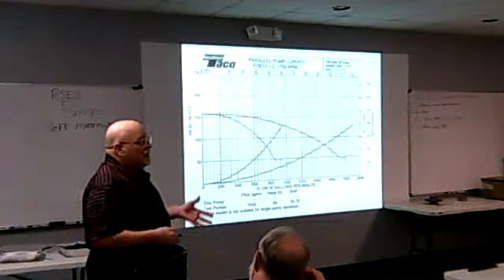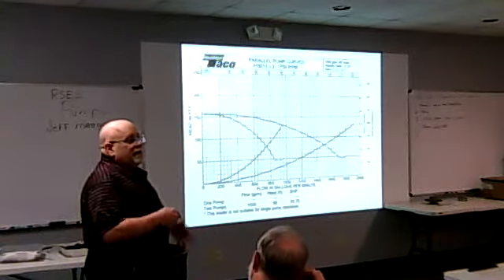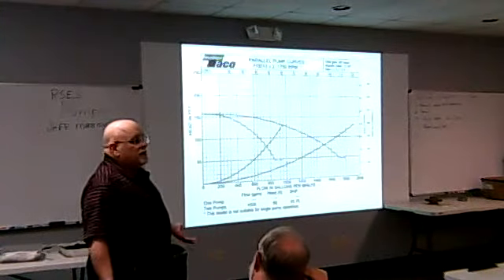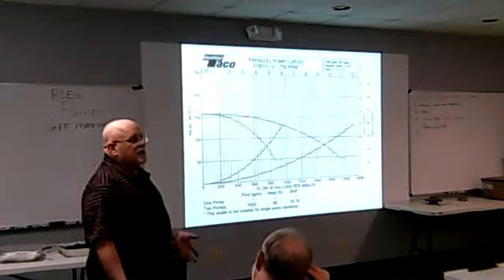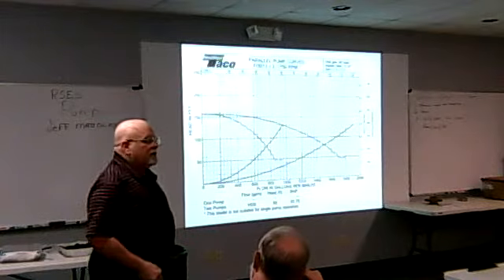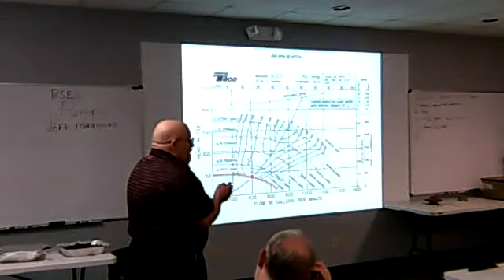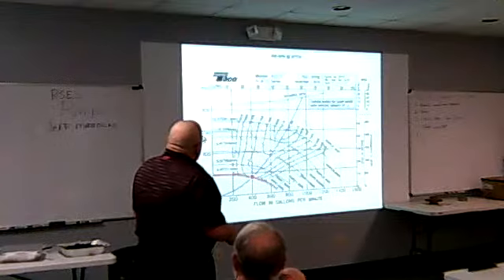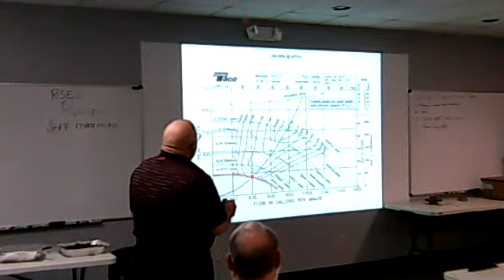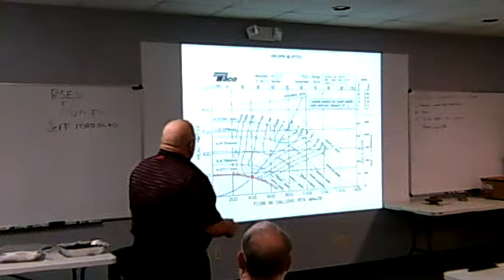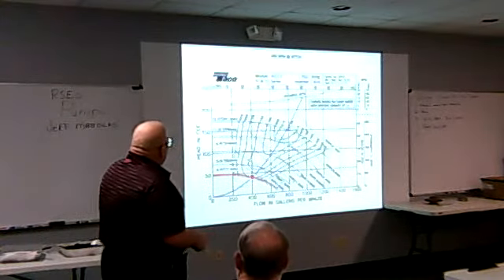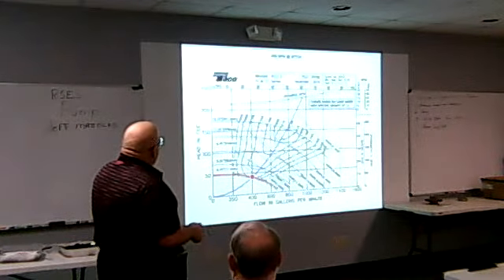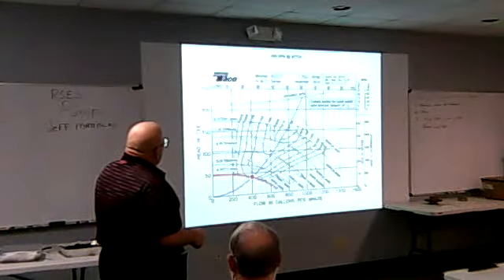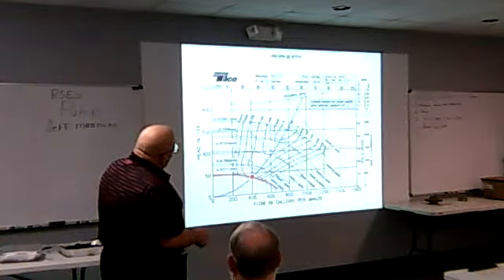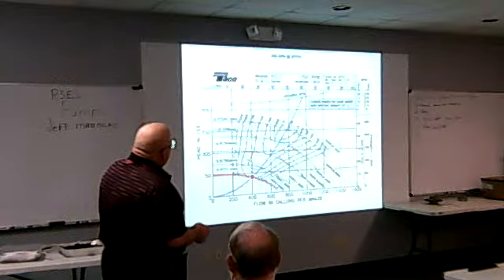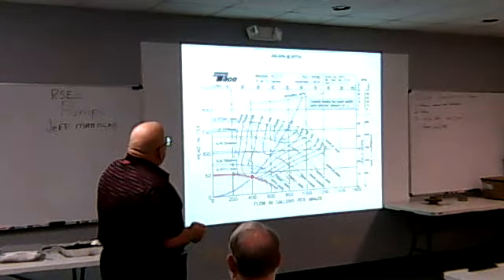When we do pump parallel selections, we look for that. We say, what happens if one pump trips? Whoops, no good. I can't get there from here. Make another selection and we find one that meets it all. Here's a selection. Now, we have 400 at 40. If I take a reading of 40 on here, and if this is my impeller, I'm not going to go out this way. For example, my next slide.